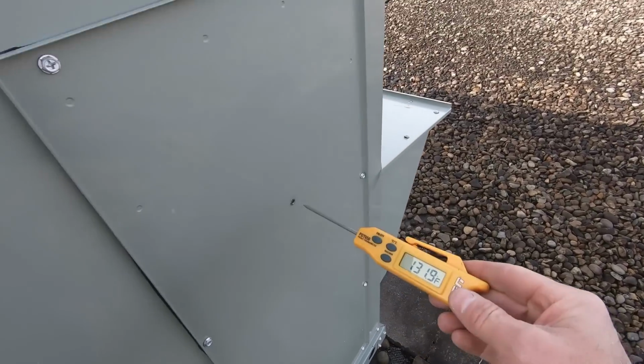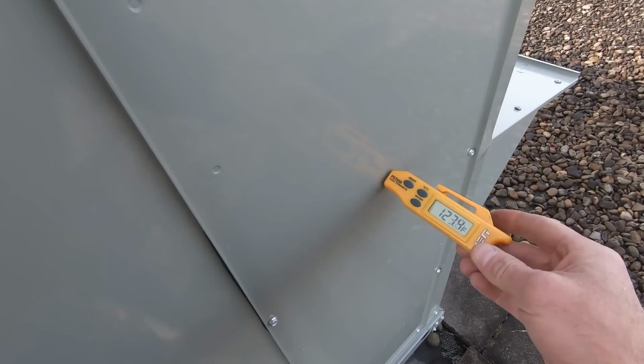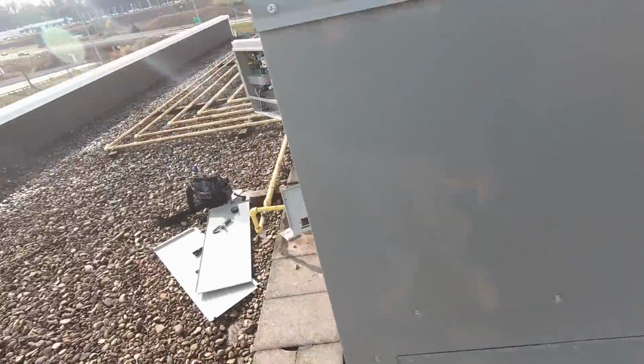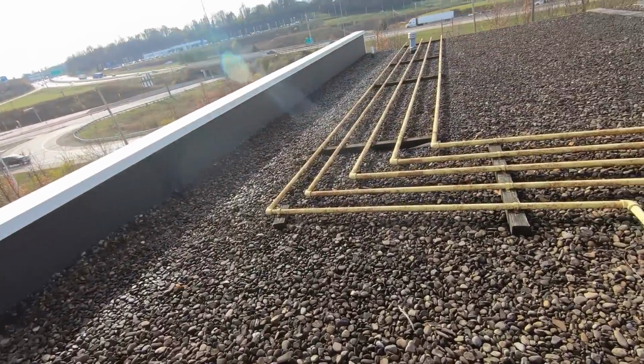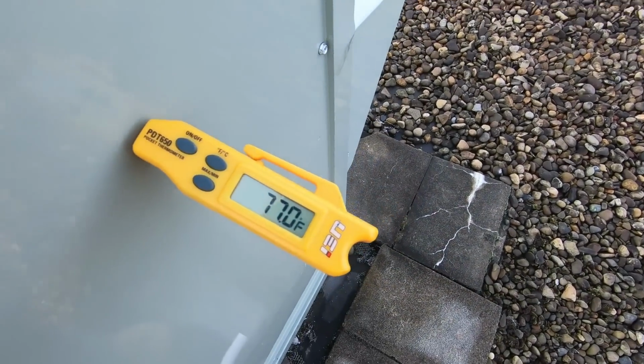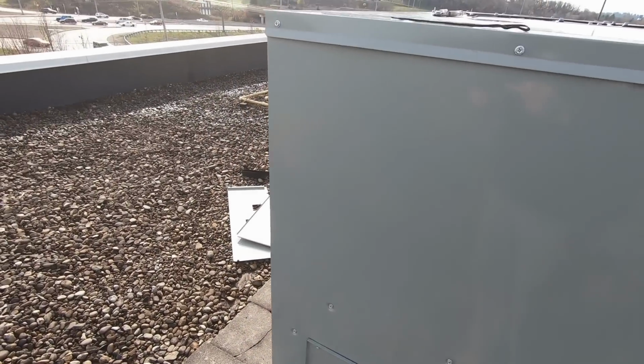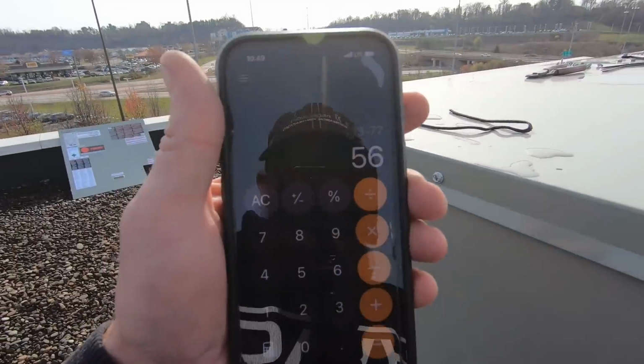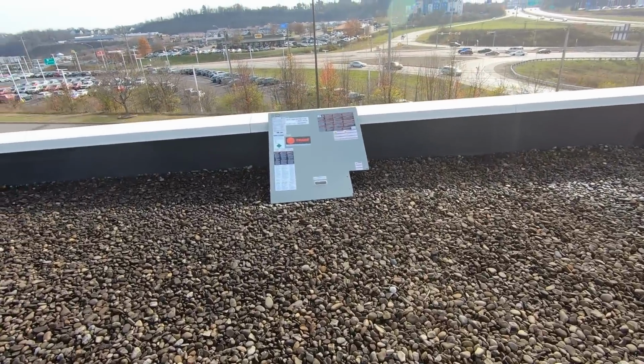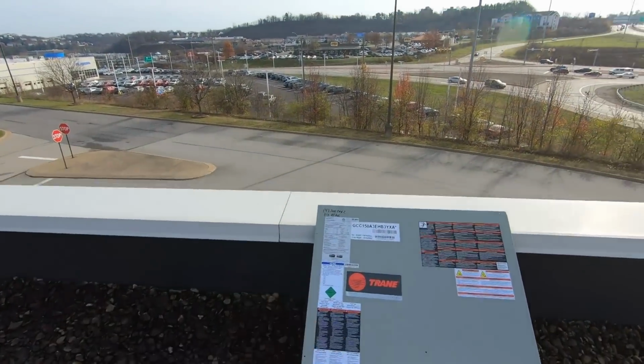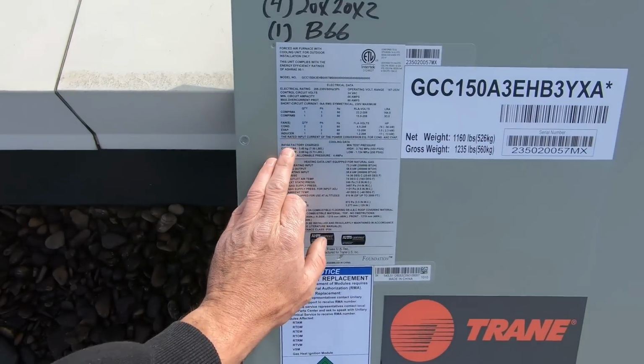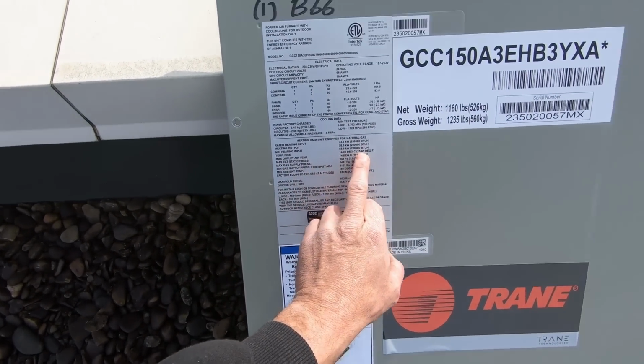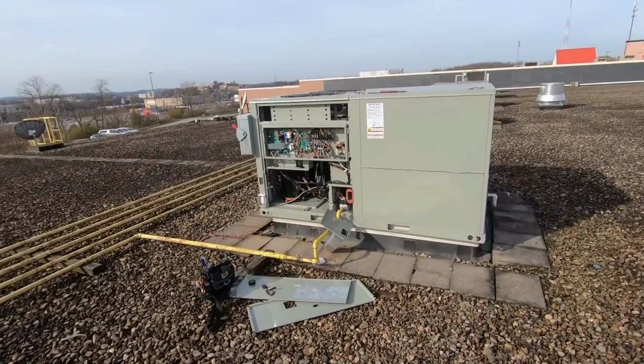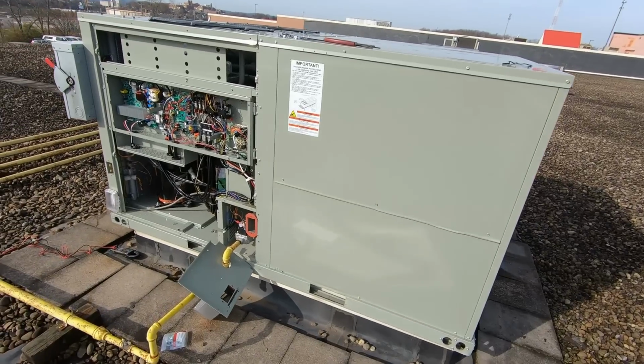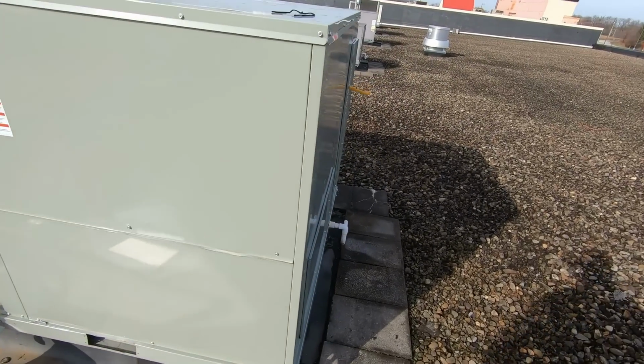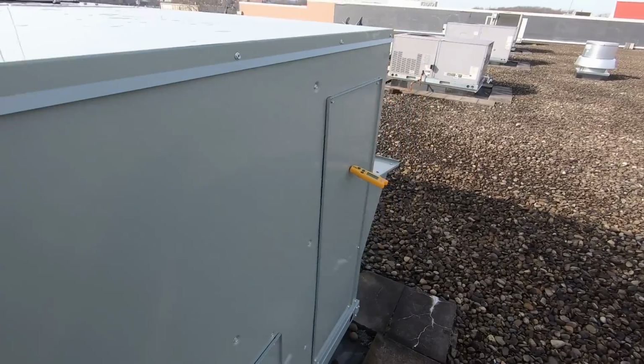133.8 is where we maxed out on our supply air temp. So we'll let that run and see what our return is and then do the math. 77 degree return, 133 degree supply. That gives us 56. 56 is within the parameters for temp rise, 25 to 65, so we're right there, and I'm good with that. I am going to recommend filters and belt and do a full startup on this.